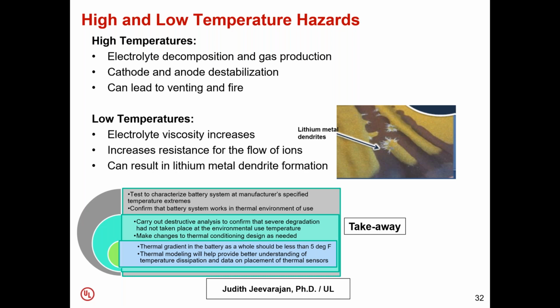The high and low temperature hazards: high temperatures can cause electrolyte decomposition and gas production in the cell. It can also cause cathode and anode destabilization, which can then lead to venting and fire. When we look at low temperatures, again, this depends on what the manufacturer specifies as the low temperature that the cell can work at. If you go below that, the electrolyte viscosity usually increases, and this increases the resistance for the flow of ions that can then result in lithium dendrite, metal dendrite formation, because the lithium ions have difficulty intercalating within the anode electrode.